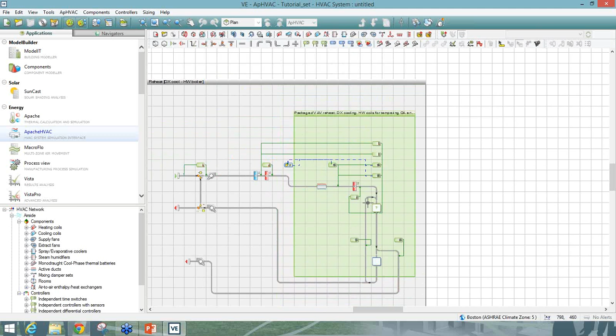But you have lots of controls. We have controls for variables such as flow rate, and we're sensing things like dry bulb temperature, CO2 concentration, and enthalpy. We have time switch profiles that can also be connected to sensors inside the spaces, so we can take the systems we've designed and really control them and see if the controls we set work well. We can also compare that to what a final building is using in the end, because often the controls part of your system isn't implemented correctly, or people are overriding it, and that's why your building isn't performing.